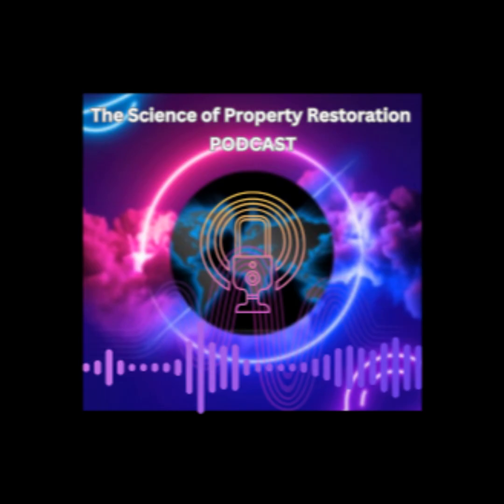And the other type? That's the newer GUV-222. It uses what are called krypton chlorine excimer lamps. The main wavelength is 222 nanometers. And the thinking there is it's safer, less harmful. That's the idea, yeah. Potentially less damaging to skin and eyes, which opens up the possibility of using it for whole room disinfection, treating the air and surfaces everywhere, even with people around.